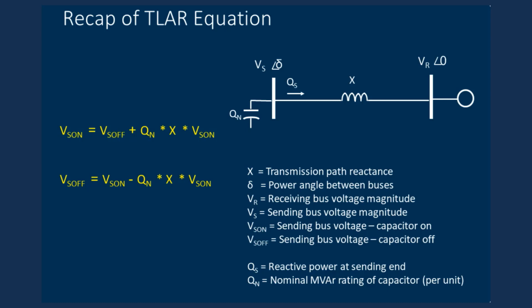We solve this equation iteratively. If there's a big increase in voltage, then we have to run this equation through a couple of times to get the final result. If we're taking the capacitor off, the voltage with it off is the voltage with it on minus the nominal MVAR rating of the capacitor bank times the reactance times the voltage with it on. In this case, there's no need for any iterations because we know the voltage with it on, and we can always get our solution with it off in a single simple calculation.